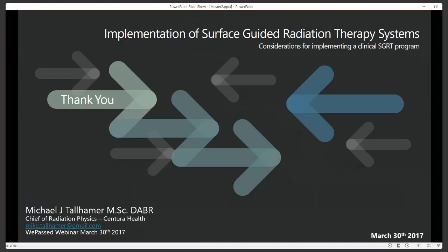Jake says, how do you reconcile alignment differences between SGRT and IGRT? On our TrueBeams, IGRT is the gold standard. We know from doing our treatment planning system surface analysis QA that if I set up using my SGRT system alone and do a cone beam CT, which I know is good down to about 0.2 of a millimeter, I should see a shift no greater than 1 millimeter in the vert, 0.6 of a millimeter in the long, and 0.3 of a millimeter in the lateral direction.